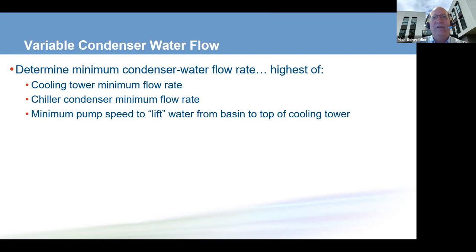The third one doesn't happen very often, but every once in a while it does, so you want to check it. And that is, in a cooling tower, from the basin of the tower up to the top of the tower is an open part of the loop. The pump needs to be operating at a speed and pressure at which it can overcome the elevation of the cooling tower, that static tower lift. And if you go below that speed, you'll suddenly get no flow rate over the cooling tower. So that's one thing to check out. Where is the pump operation going to be? What's its minimum pump speed to make sure we overcome the tower static lift?